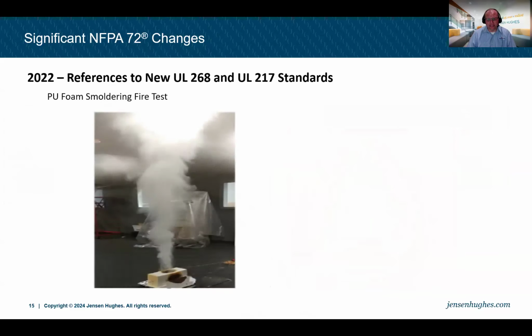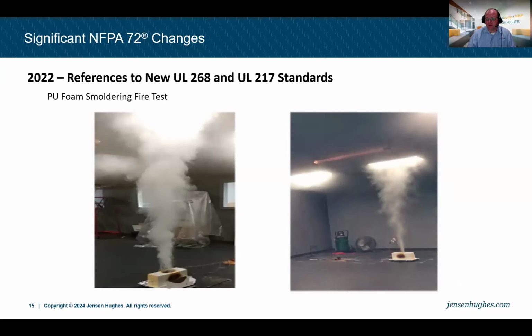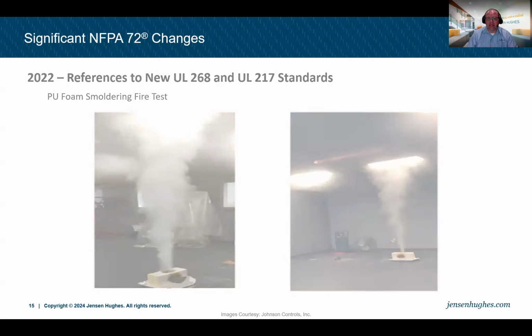Similar with the smoldering test, this is a smoldering polyurethane foam. It produces a different color, different type of smoke. Here you see some pictures from the actual test chamber. And we do want our detectors to alarm when it comes to this. So really the whole breadth of the smoke detector market has been updated to make sure it's not overly sensitive to nuisance alarms, but it is reacting properly to the construction materials that we're using today.